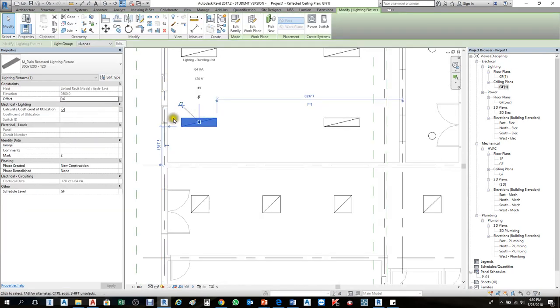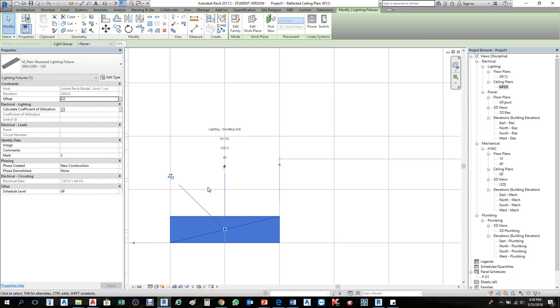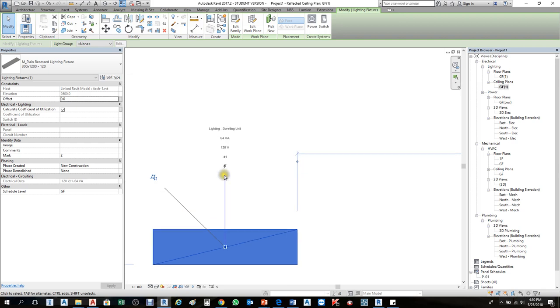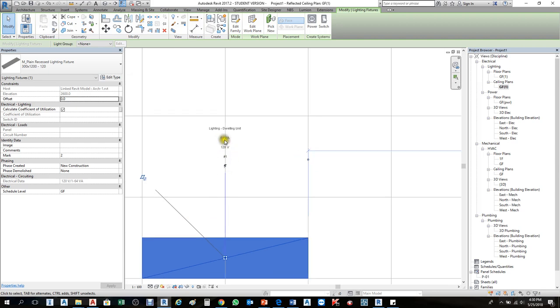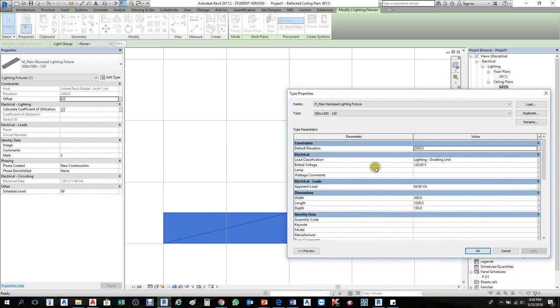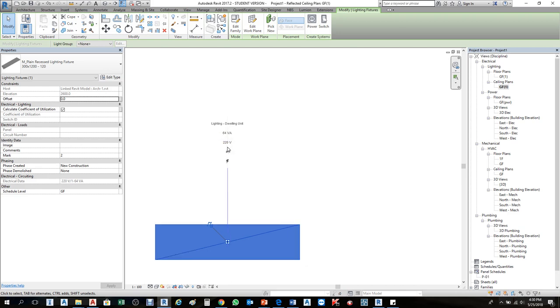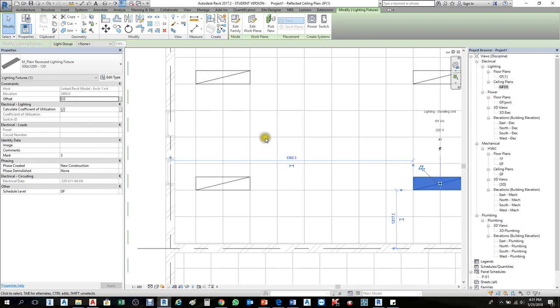When you select this lighting, notice the difference between an MEP lighting fixture and an architectural lighting fixture. If you select the MEP lighting fixture, it shows 120 voltage, 64 VA — voltage, ampere, and lighting dwelling unit are already mentioned for the calculation. So it will go to our panel based on this loading. If you go to Edit Type, the ballast voltage is listed as 120. If you change it to 220, it will apply to all lighting fixtures of that type.